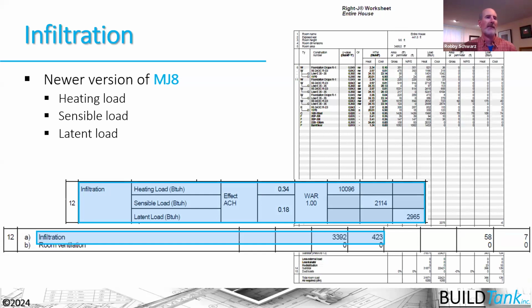But we can see that the heating load is being measured in air changes per hour at 0.34, and the sensible and latent loads, which are basically the cooling loads that are associated with the moisture that's in the air, are at 0.18 air changes per hour. And we can see that the loads associated with them range from 10,000 to 2,100 BTU hours here.